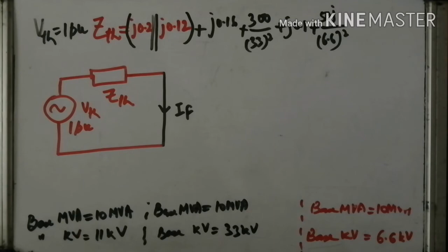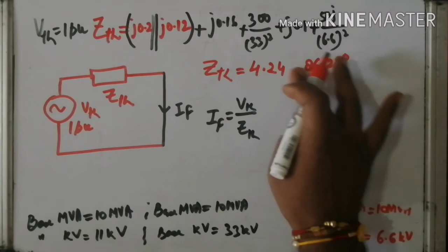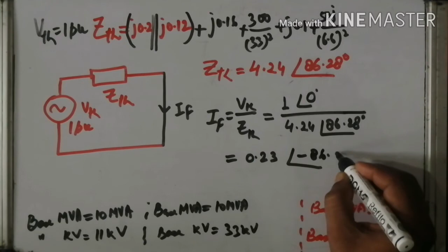After the calculation, the value of ZTH is 4.24 angle 86.28 degree. After the calculation, this one is the value of Z. That's why the fault current is given by the formula VTH divided by ZTH. What is the value of VTH? It is 1 per unit, so it is 1 angle 0 divided by this one, that is 4.24 angle 86.28 degree. After the calculation, it is 0.23 angle minus 86.28 degree. This is the value of current.